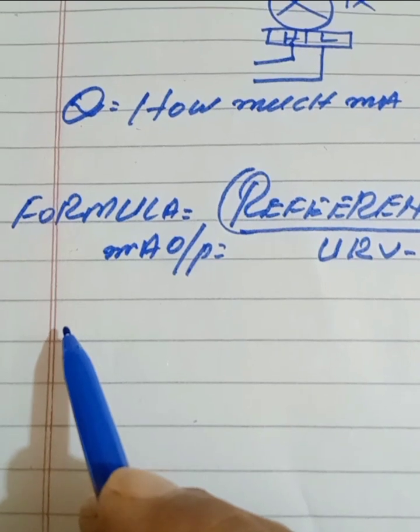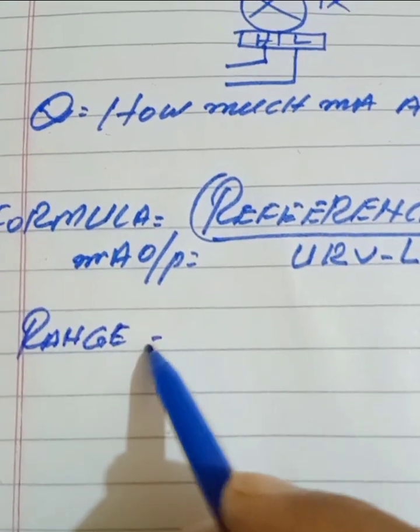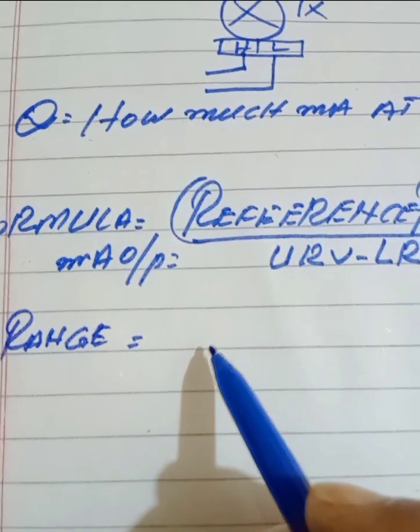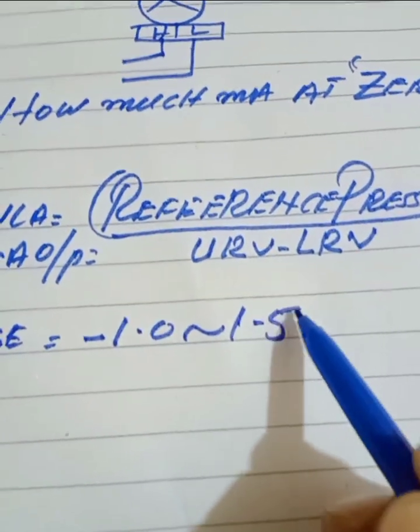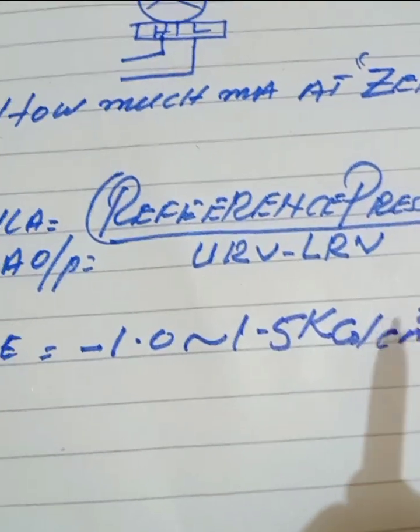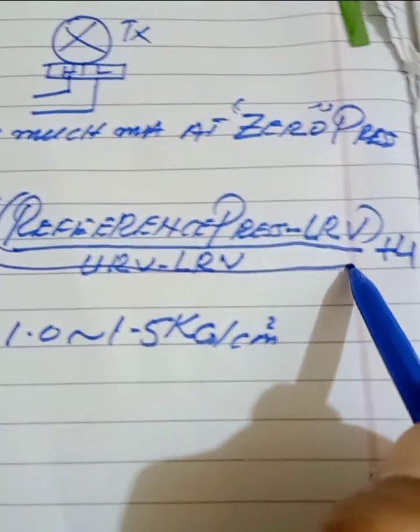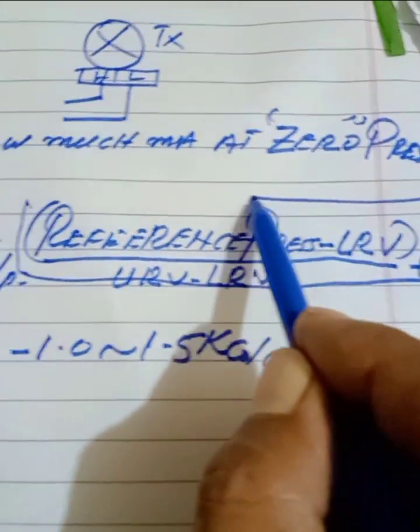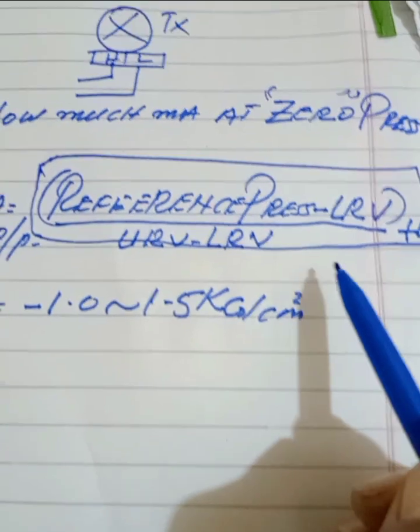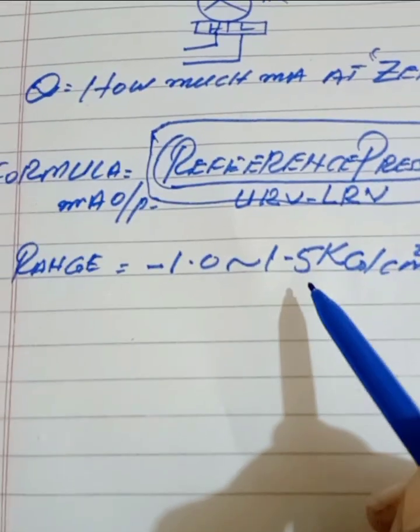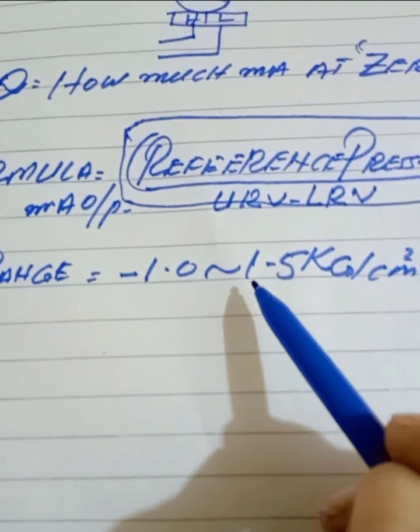Suppose our transmitter range is minus 1.0 to 1.5 kg per cm squared. As per this formula — reference pressure minus LRV, divided by URV minus LRV, multiplied by 16, plus 4 — we will calculate how much the current output of our transmitter. Our transmitter range is minus 1.0 to 1.5 kg per cm squared.